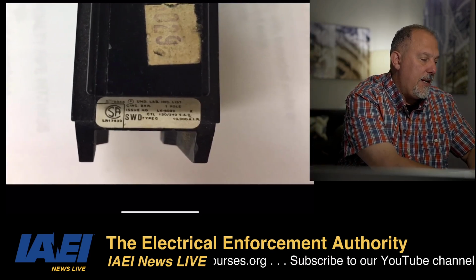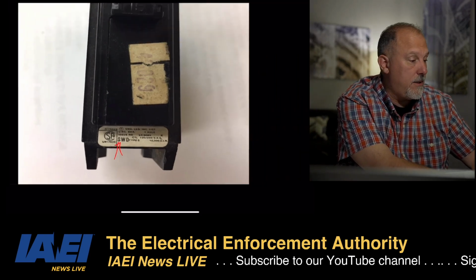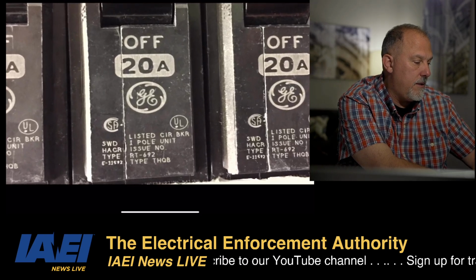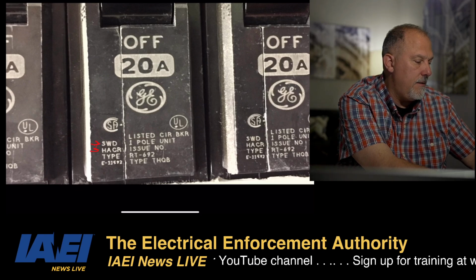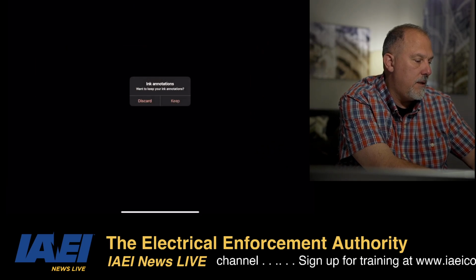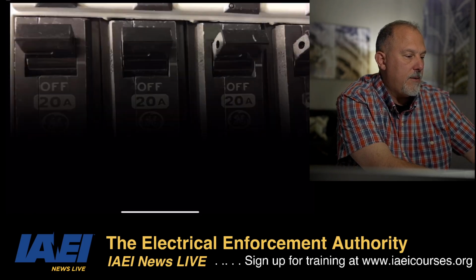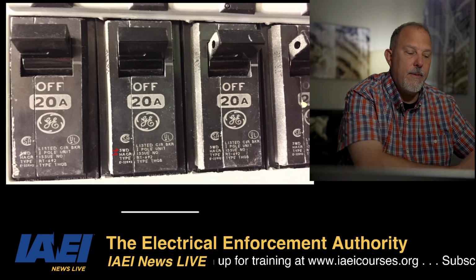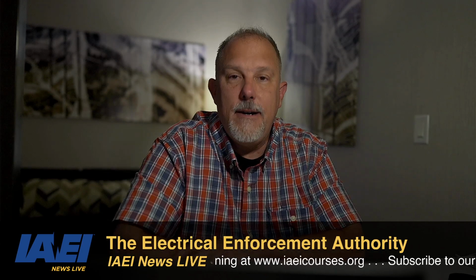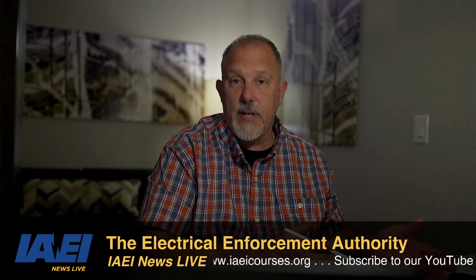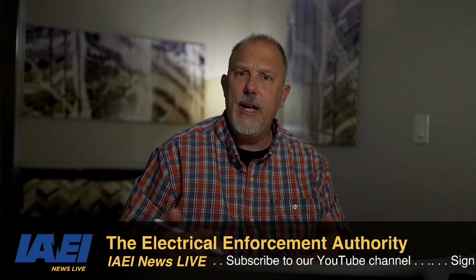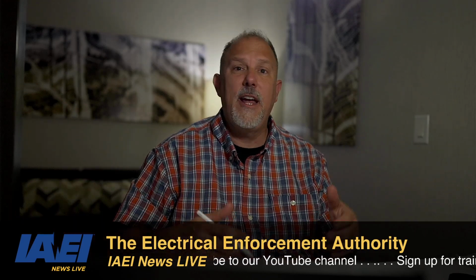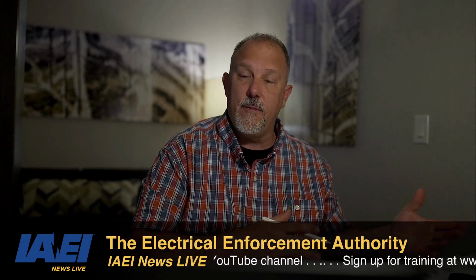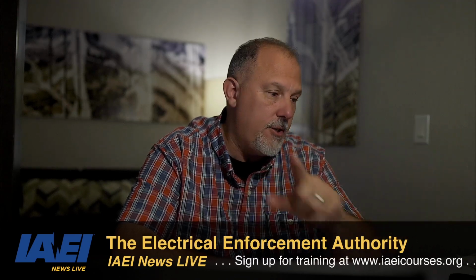There you go. So there's an SWD down here. That's a switch duty. That's your fluorescence. Here is HACR SWD. These are all SWDs. Let me go back. All right, so I think that answered that question. We saw SWD and HID, and if I go back and look at SWD, you're going to see that there's a specific type of load, which is your fluorescence, your compact fluorescence and your fluorescent tubes. It's switch duty. It has to go on and off. We test those at a specific power factor and for a number of cycles, just like we do HID. The HID is a different power factor. So we match the test with the type of load, and we cover endurance.